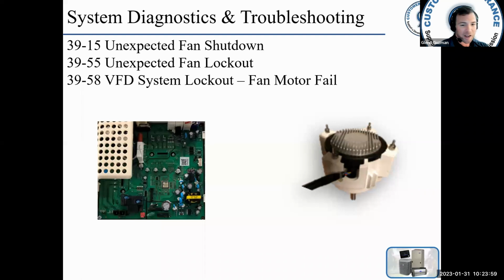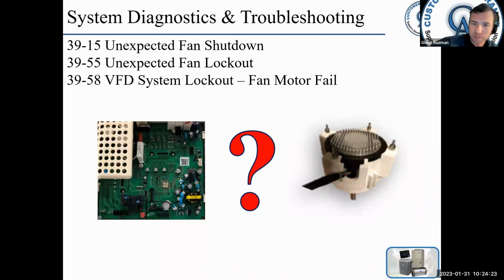Here's where I don't care for what the manual tells you. It says internal electrical damage is likely causing the FG feedback to not be received by the VFD. Replace the fan motor first, then the VFD. To me, that's not definitive enough, but if you run across something like this, give us a shout and we'll try to help you out best we can.